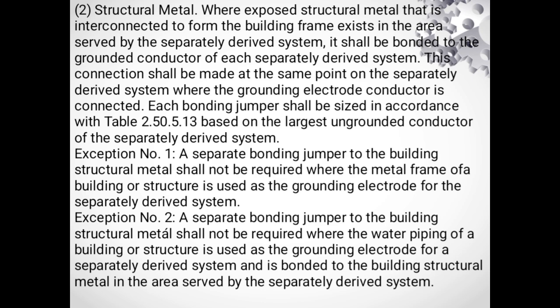Exception number 1. A separate bonding jumper to the building structural metal shall not be required where the metal frame of a building or structure is used as the grounding electrode for the separately derived system. Exception number 2. A separate bonding jumper to the building structural metal shall not be required where the water piping of the building or structure is used as the grounding electrode for a separately derived system and is bonded to the building structural metal in the area served by the separately derived system.